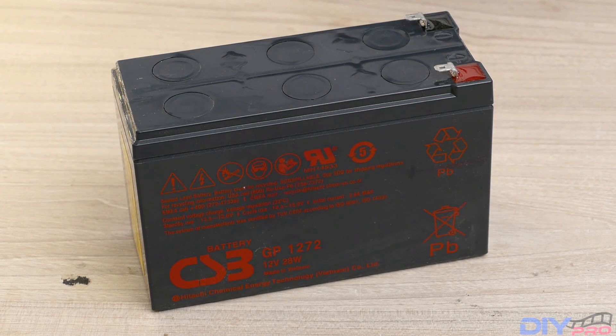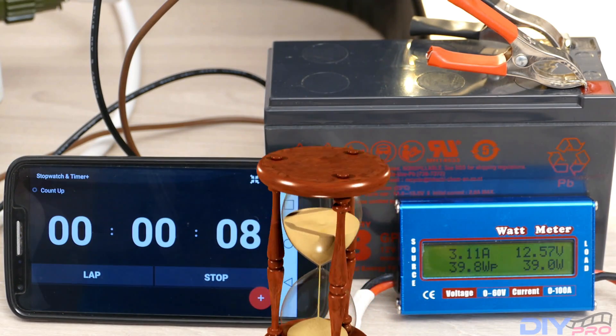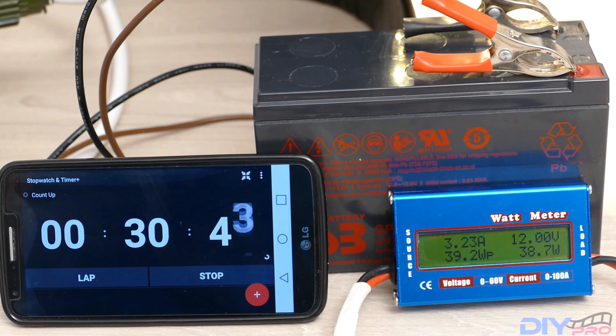The CSB battery is usually found in UPS units from APC and it's very common. I'm using my LED light as the device drawing current. We started with 12 volts on my meter, and after about 30 minutes and 45 seconds we've got below 12 volts.